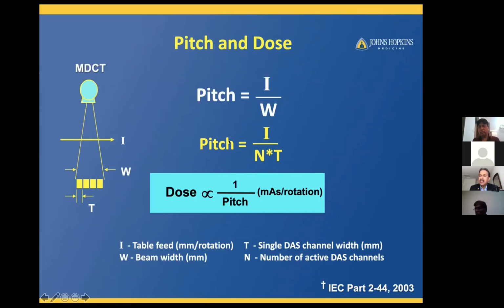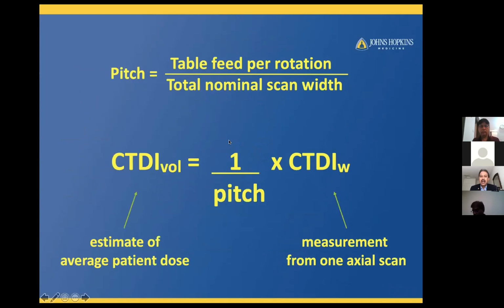The reason why pitch becomes important is we need to incorporate it into the CTDI calculation, and we have the term called the estimated average patient dose, called the CTDI volume, and that's given by the formula, the CTDI weighted divided by the pitch. So basically the pitch is incorporated into this particular measurement to get the descriptor called CTDI volume. And this is one of the key dose descriptors in CT.